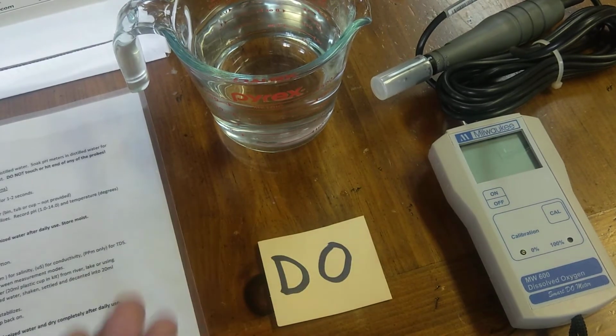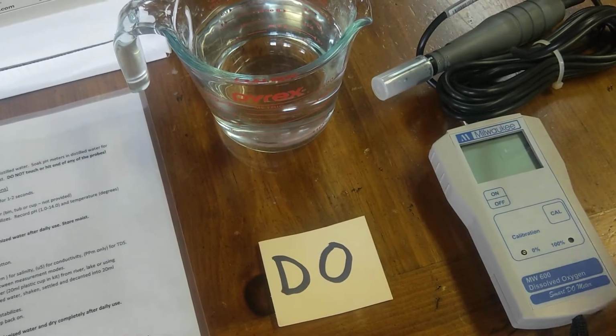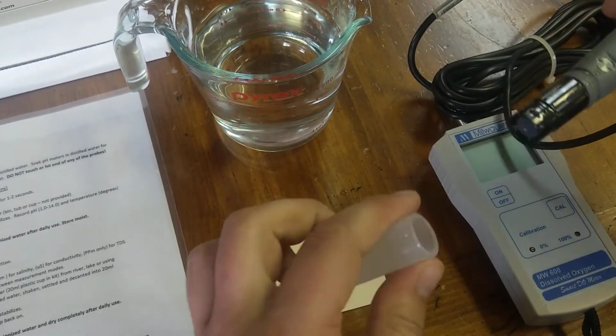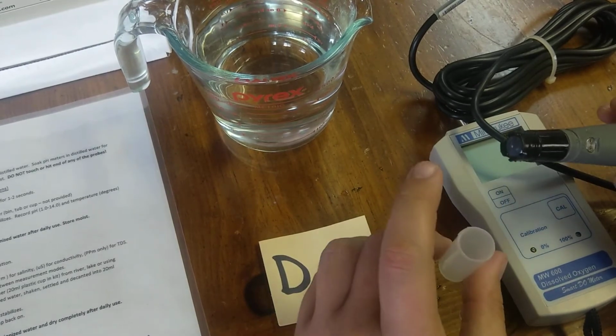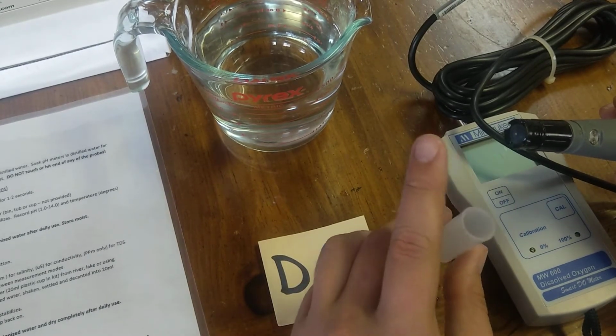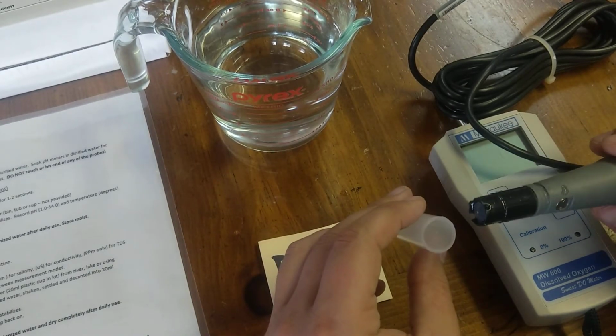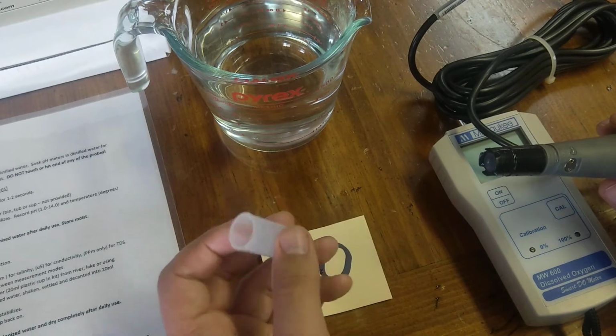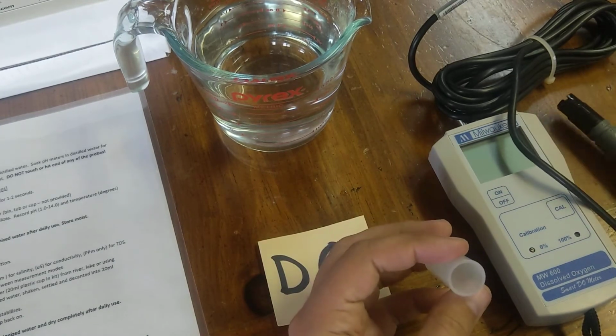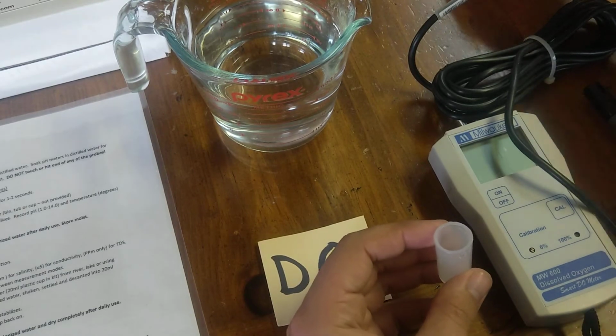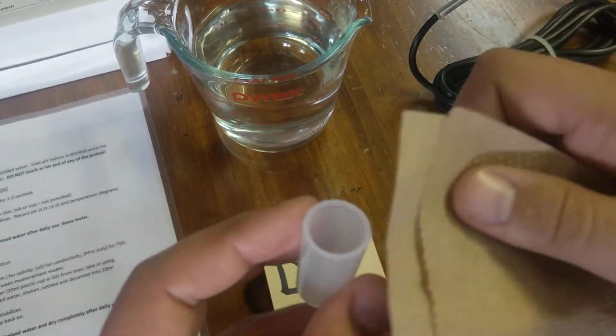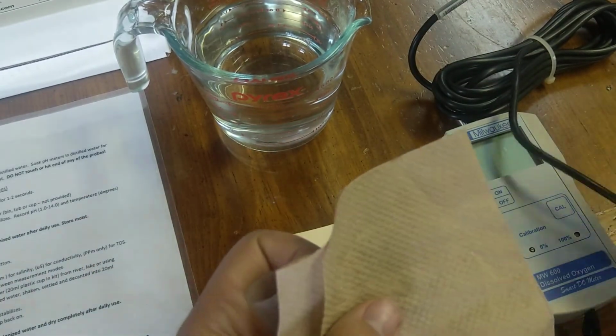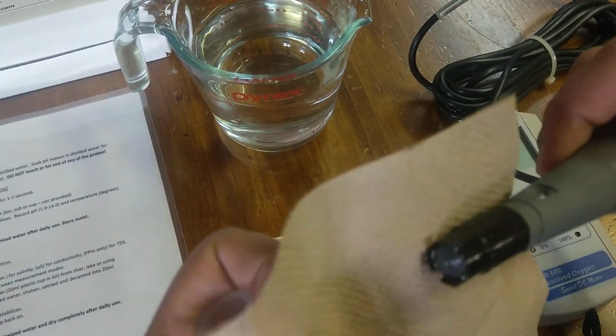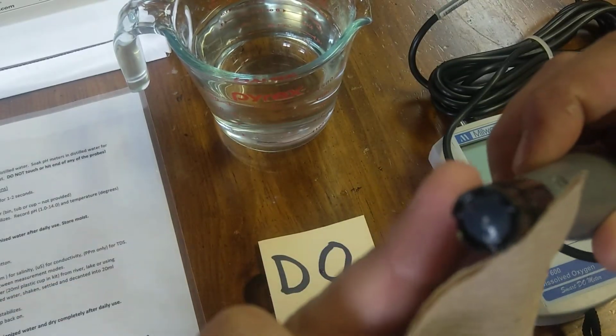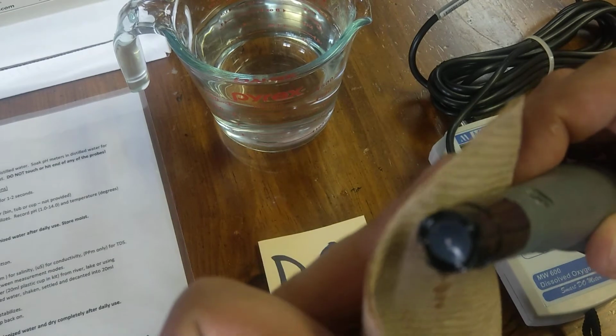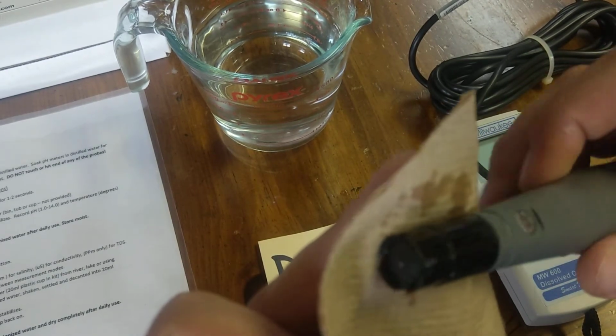So for general, everyday maintenance, you can dry this all out. I would just do a quick air dry kind of thing. If it's a little bit wet, that is totally fine. Again, you're trying to reduce the amount of molds and algae in here. So sometimes what I'll do is I'll go in with a paper towel like this and just dry the inside. I would dry just the outside with the paper towel. I will not touch the end of that sensitive probe there, because this might lacerate some of that and affect your readings. So just the outside over here.